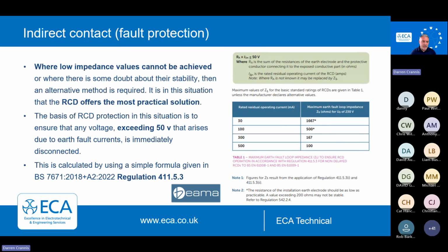Looking at indirect contact, for those who are old enough, or fault protection, as we refer to it today. And this is the key point of this. It's where disconnection times or your Zs values cannot be reached, and often they're exceeded. So we use the RCD for fault protection. We've been doing this for years with TT systems, where there's an earth electrode and it's a high impedance value. So therefore, we tend to put that 100, 300 milliamp time delayed RCD at the front of our installation.